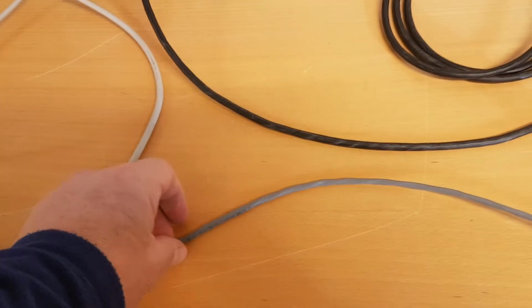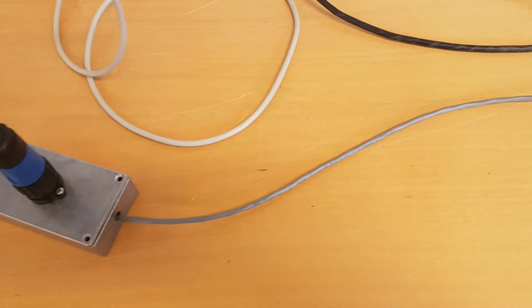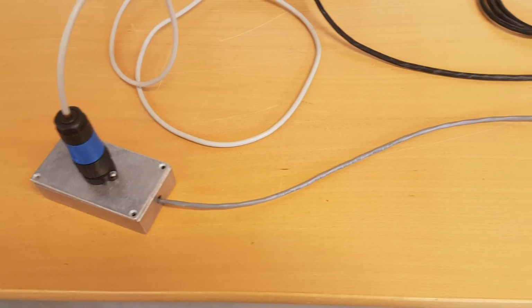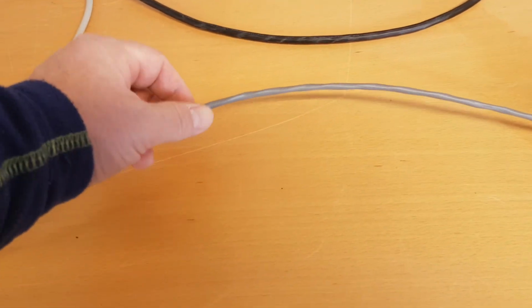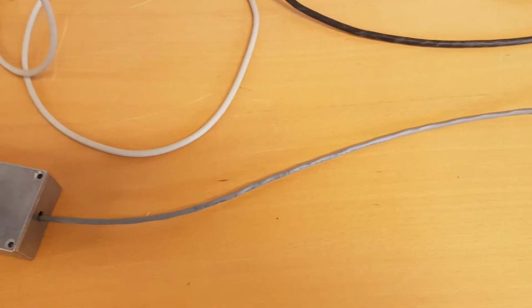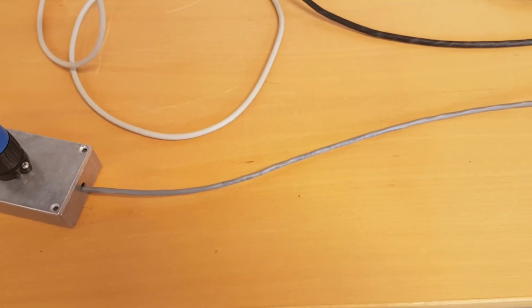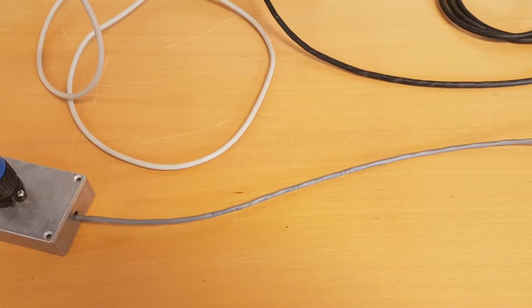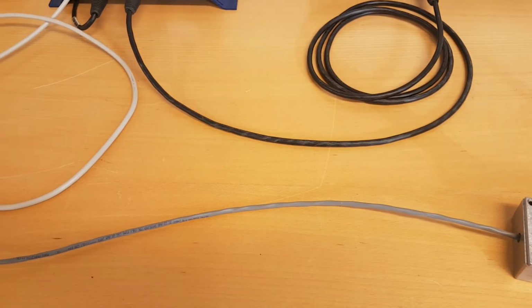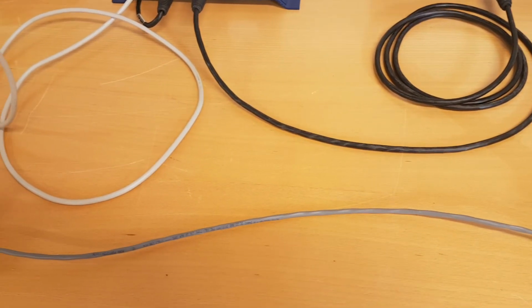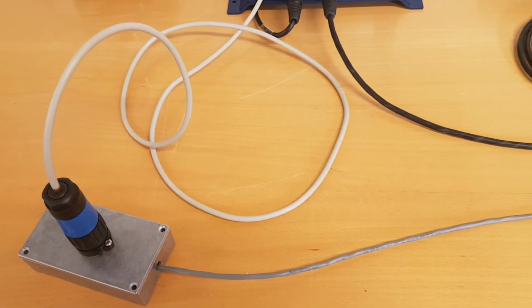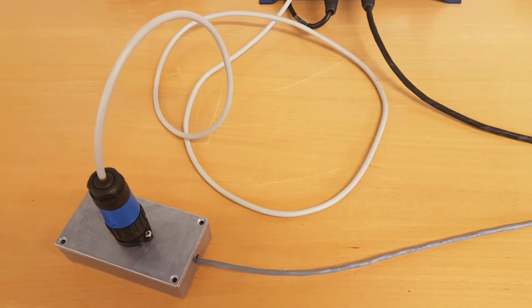It might be an indoor cable which is buried or even put in conduits underground, where water will be occurring, and even though you have a plastic or rubber sheeting on the cable, water will penetrate the cable and over time change the properties of the cable, and this might destroy the signal carrying capabilities of the cable. And even though we can measure it for resistance and so on, it looks okay. Signal wise, it might be completely defective.